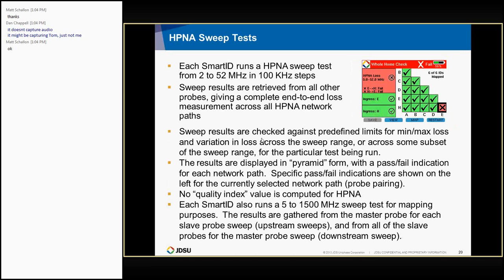HPNA Sweep tests are similar, except they are run on the HPNA band from 2 to 52 megahertz in 100K steps. These sweep results are gathered up and checked against the predefined limits for min-max loss, loss variation, and other parameters which can optionally be defined for determining whether the test passes or fails across that band.